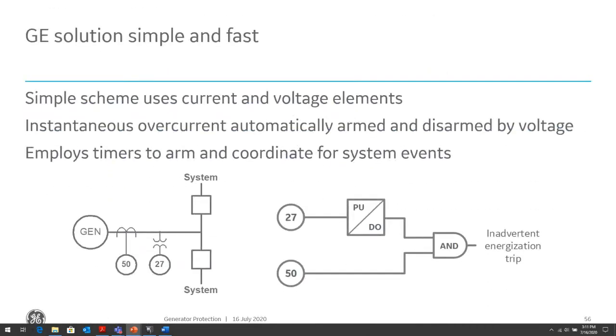And the way we detect this is a fairly novel method of detecting energization. We know when we de-energize the system, either the breakers open up or we have an undervoltage condition. Once we take the generator out of service, we enable the inadvertent energization protection.